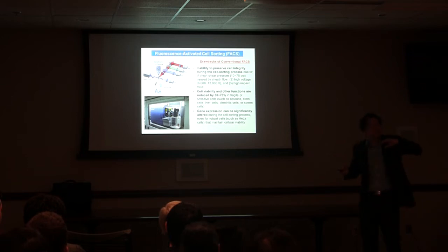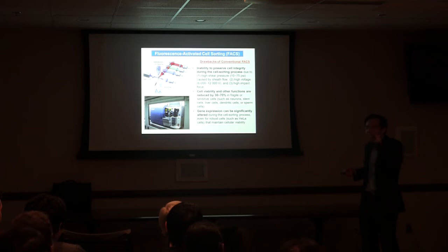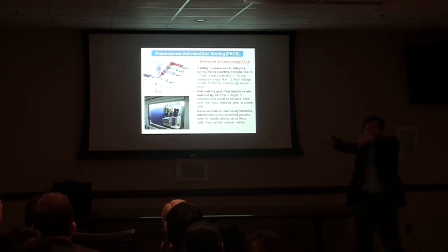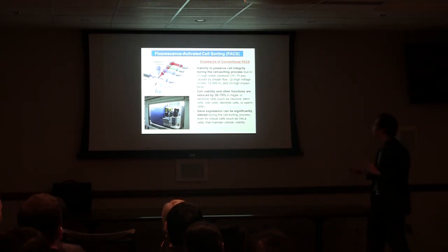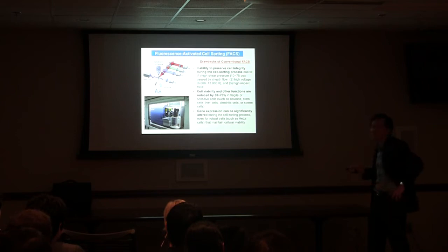So if you really need to do sorting, the ability to preserve cell function is very, very important, because if you cannot preserve the cell function, you can't sort it. And the reason why they cannot preserve cell integrity is because the shear pressure used to squeeze the biological cell is very, very high - it's 70 psi. And also the voltage applied is very high, 6,000 to 12,000 volts.